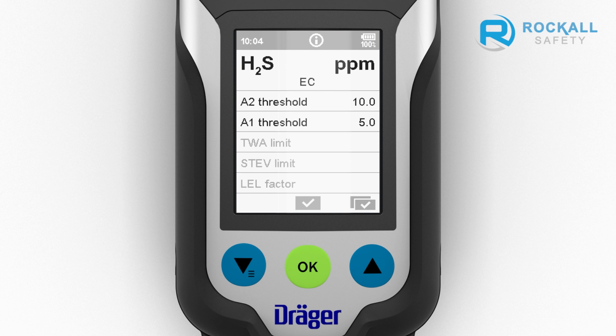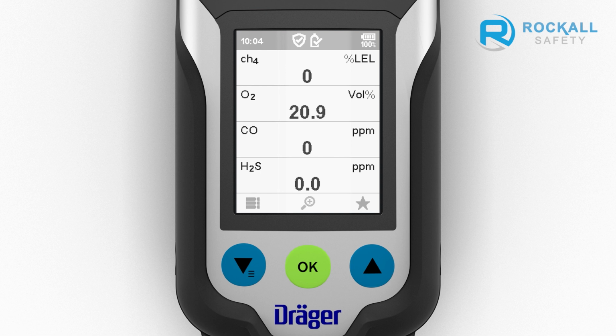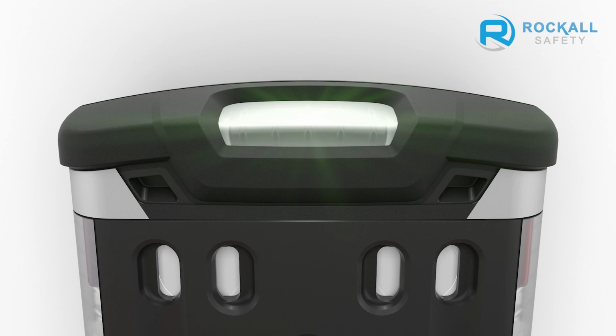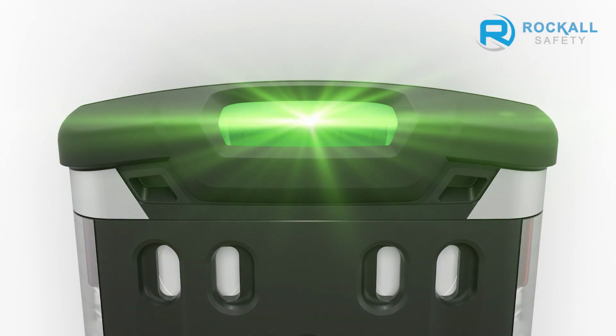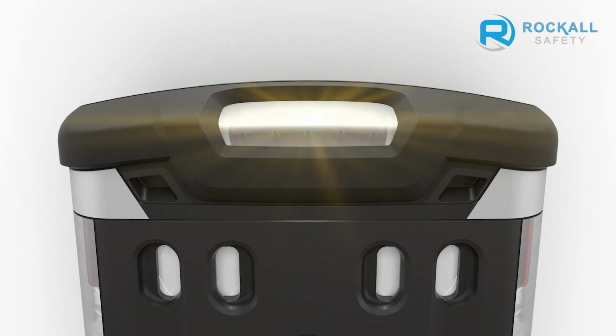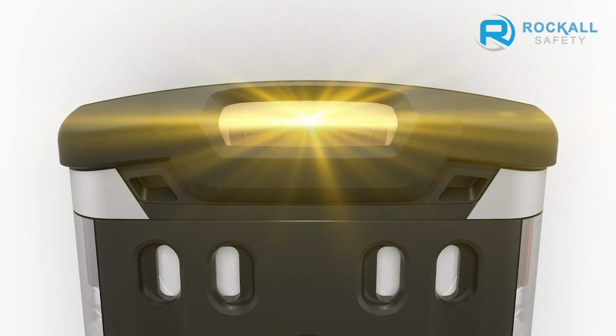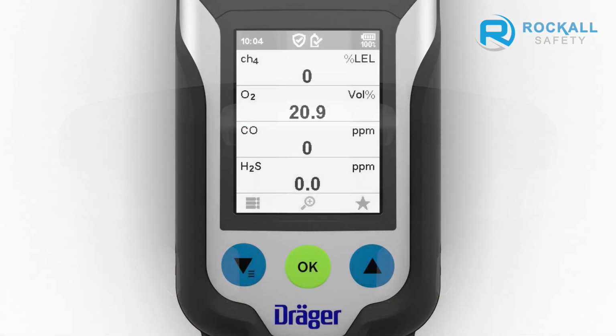The device is now in measuring mode. To activate measuring mode quickly, the alarm threshold display can be skipped. The device is ready to start measuring when the green LED at the top of the device illuminates. An illuminated yellow LED indicates that the X-am 8000 is in a special state, warming up the sensors for example.